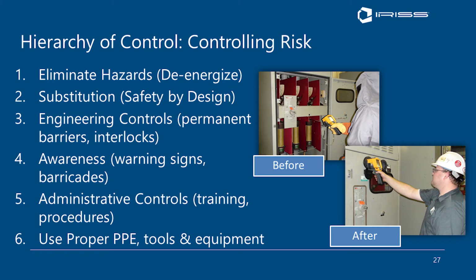Well, it doesn't reduce the fault level, but it decreases the trip time, which reduces the arc flash incident energy level. So all these little tricks and things we can do to reduce the risk, but not necessarily eliminate it. All of that is engineering controls.